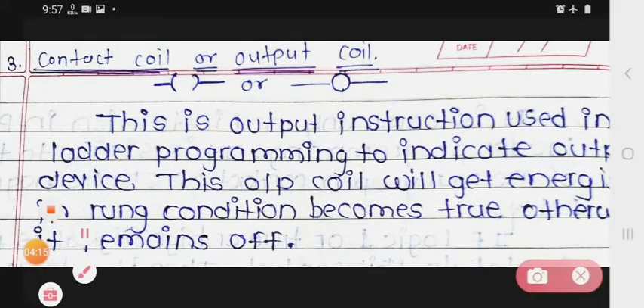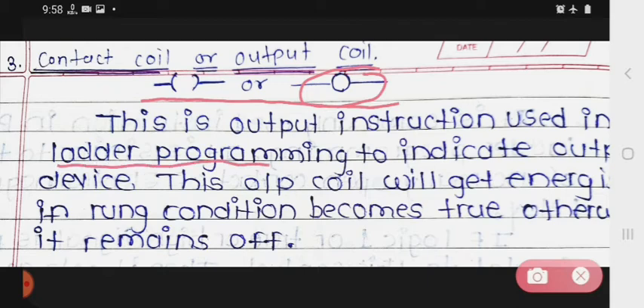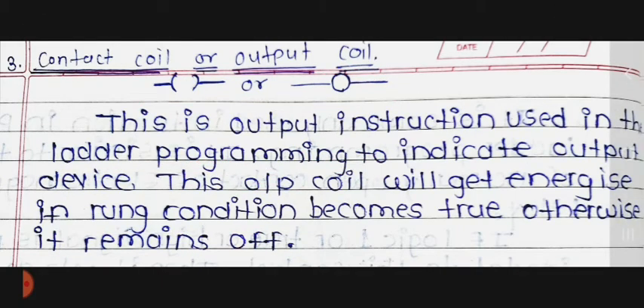The third instruction is the contact coil, also called output coil. This is the output instruction used in ladder programming. It indicates the output device. This output coil will get energized when the rung condition becomes true; otherwise it remains off.